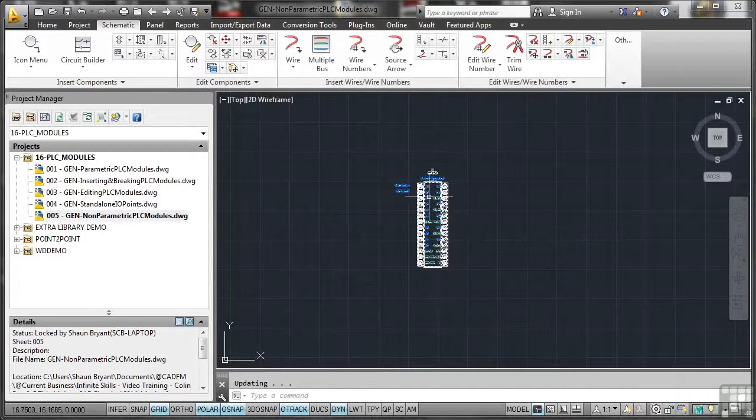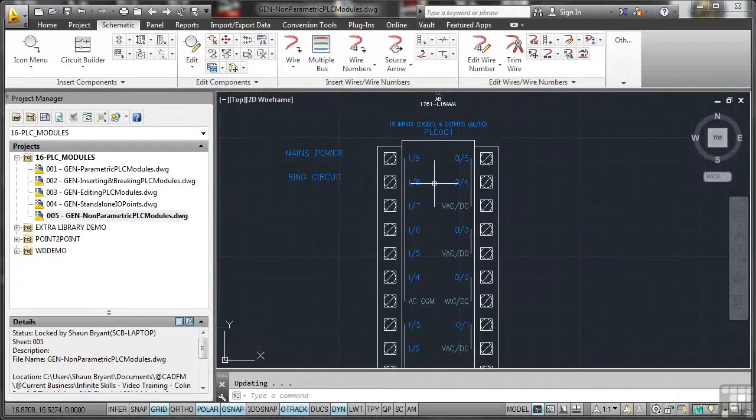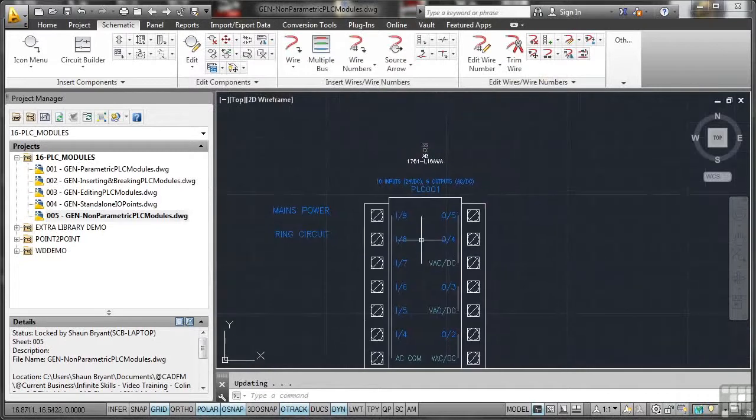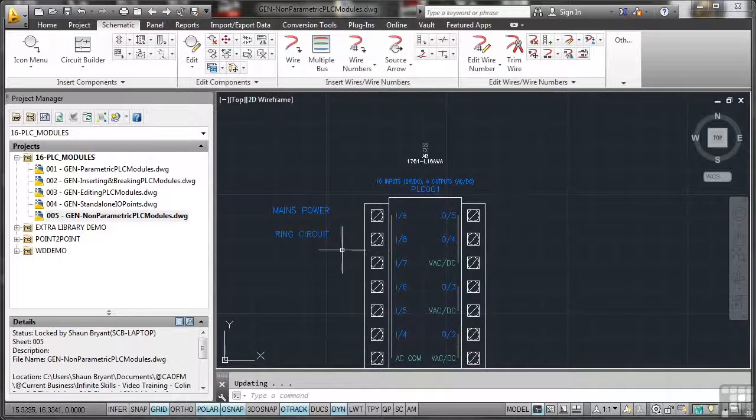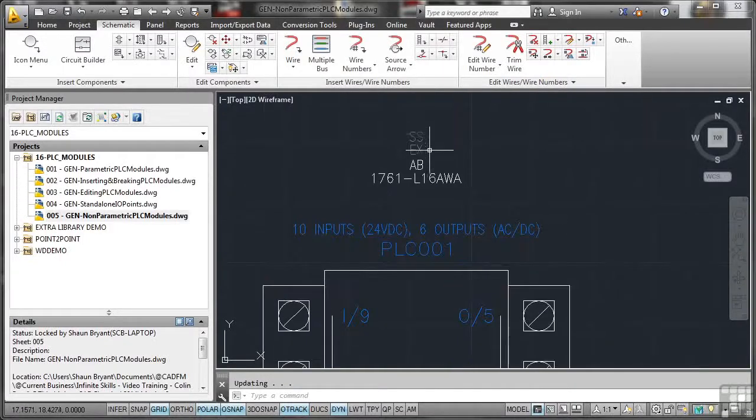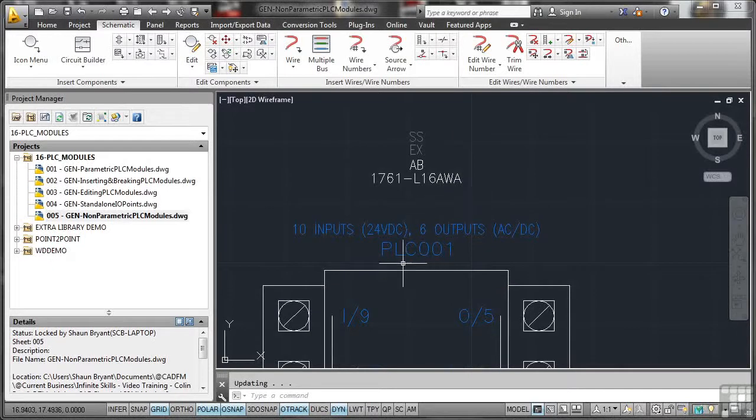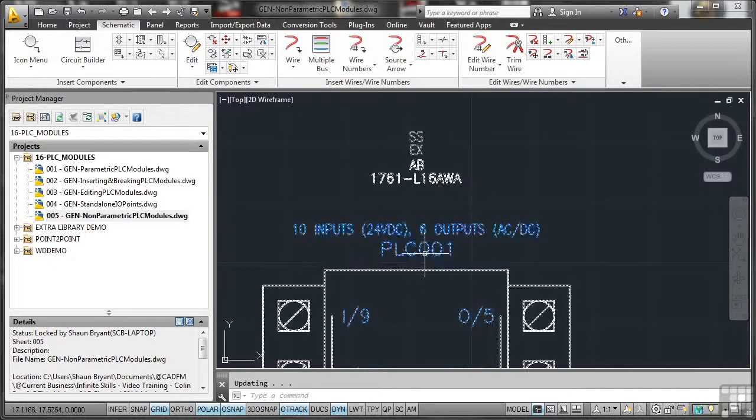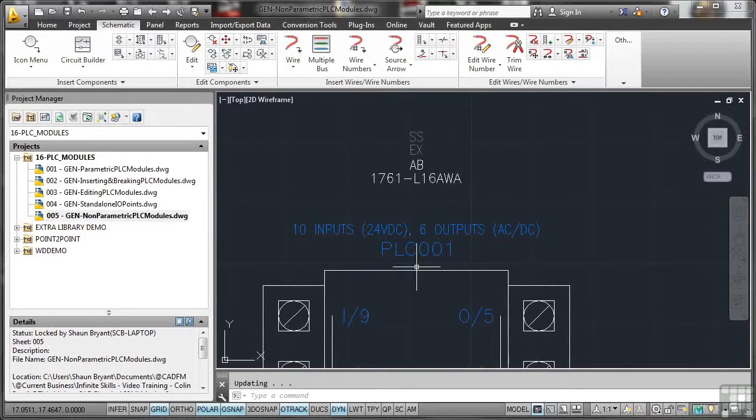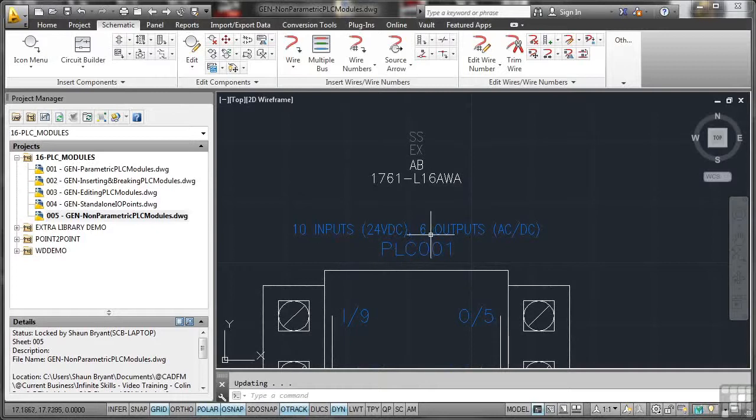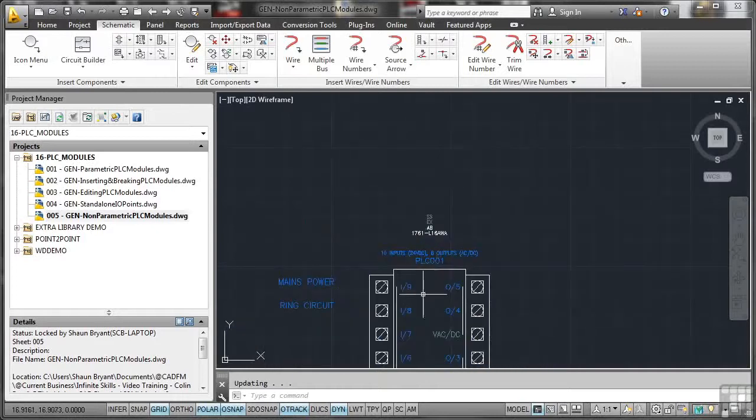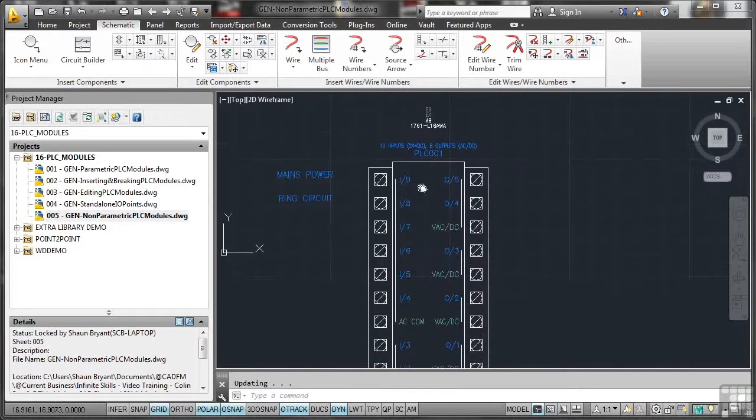it updates. And if I zoom in, we can see things like, there you go, I9, mains power, ring circuit. It's just telling you where those connectors go. And there, you can just see there, SSEX, installation and location. And there's the PLC001. It tells you it's 10 inputs, 24 volts DC and six outputs, ACDC. So all the information is there that you need.